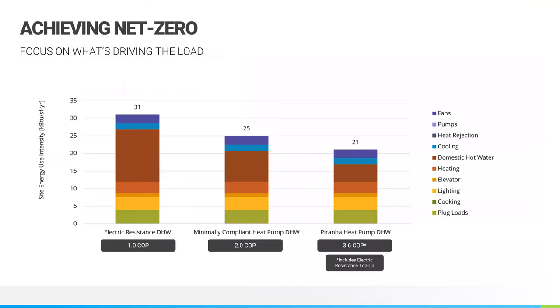And really the next slide hits it home for the developers that are pursuing that net zero design. So one thing that you'll find, though this is in Boulder, the cooling loads are obviously relatively small, but even the heating loads are smaller because of the construction of a net zero building. Because these buildings are so much better built, have a lot less heat loss, they require less on the space heating and cooling.